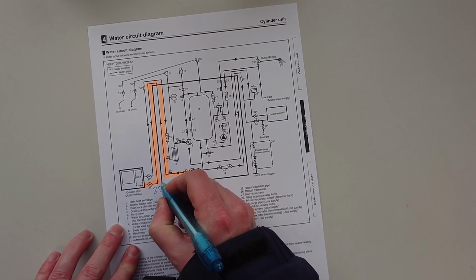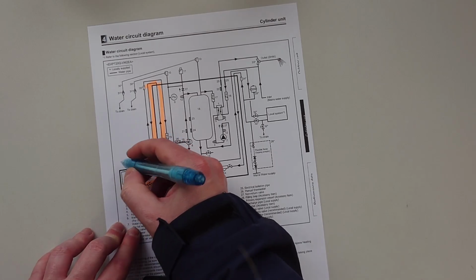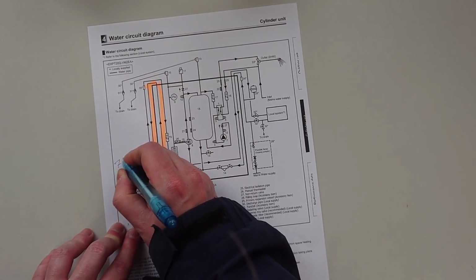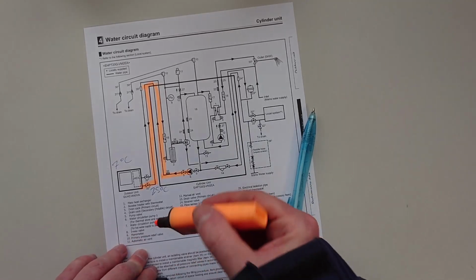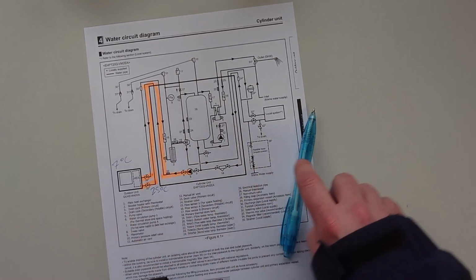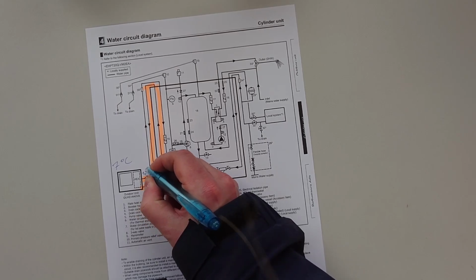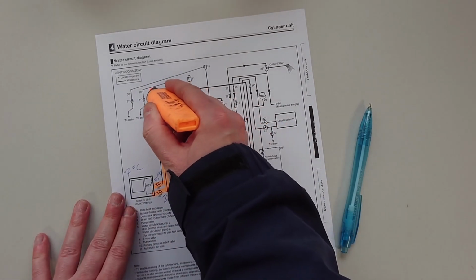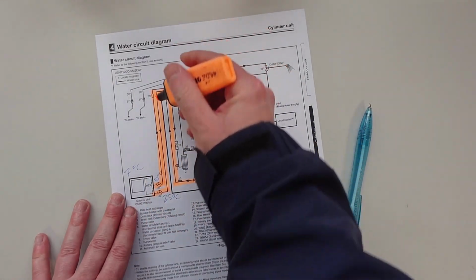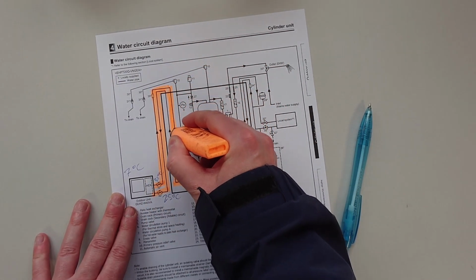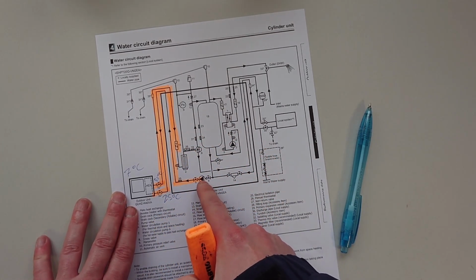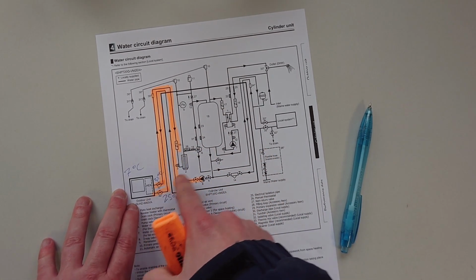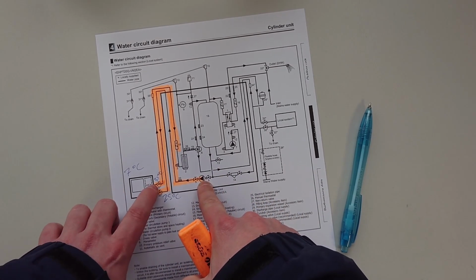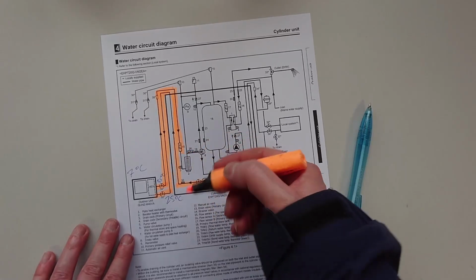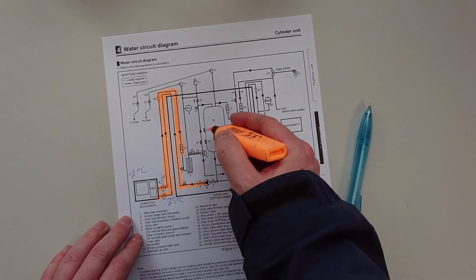Now this, at the rating condition here, is 25 degrees C water going in, and the air outside going onto it is 7 degrees C at your rating condition. And then when we come out of here, which is the water return to the system, this is your 35 degrees C part. So that's your standard rating condition, and we go back into the heat pump itself, down here, through the flow meter, which is partially used to check that this pump's actually working, because if they don't detect flow there, they know there's a blockage somewhere. Either the pump has failed or these valves are closed because the bloke serviced it and not opened them again, or whatever, some reason, not flowing, error code comes up.